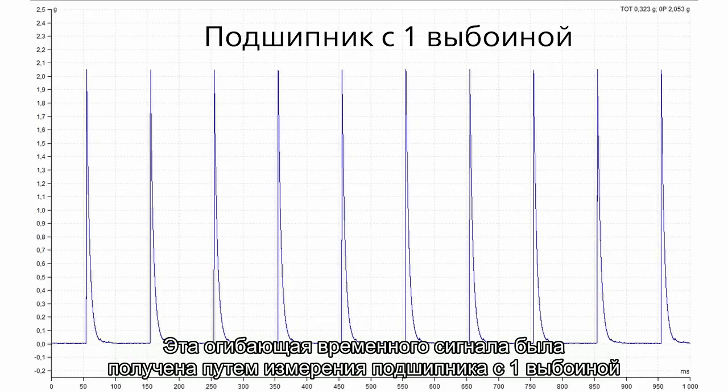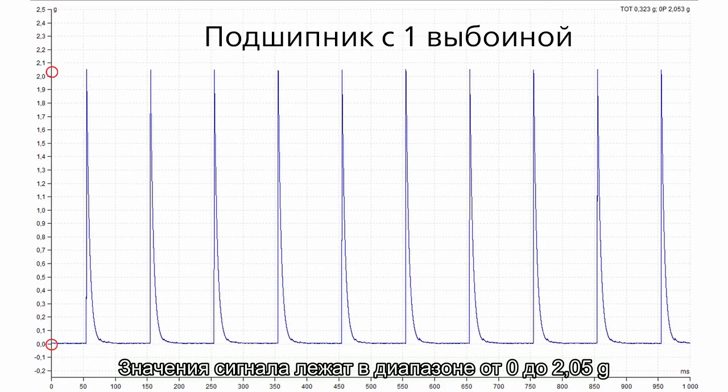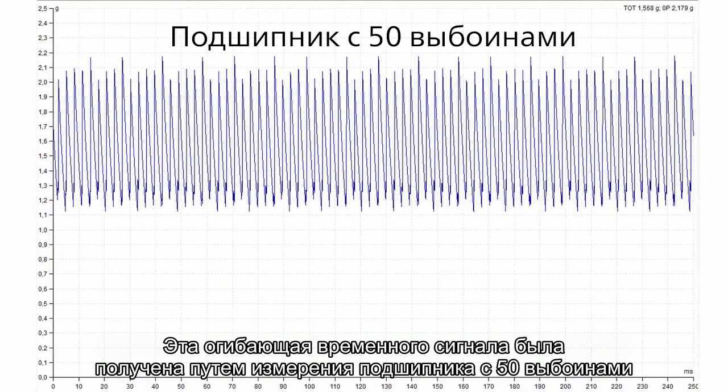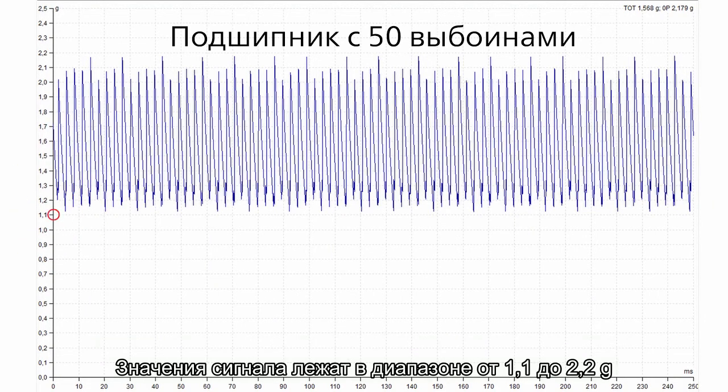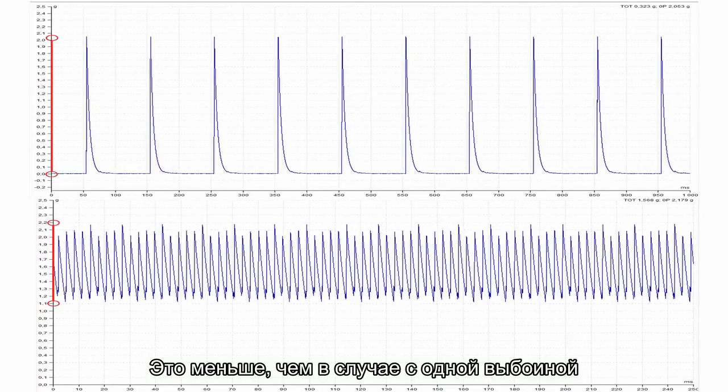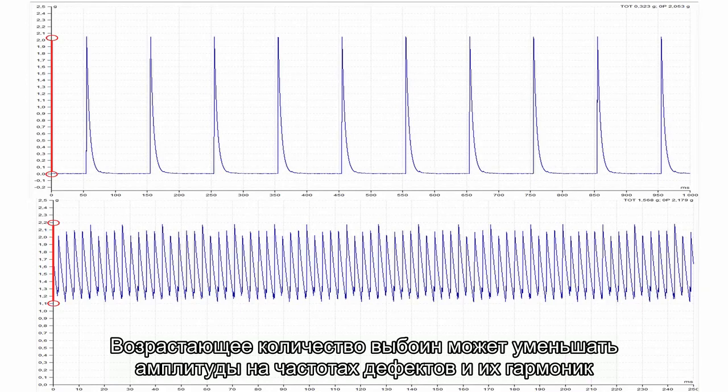This enveloped time signal was taken from the bearing with one crack. The signal range is from 0 to 2.05 G. This envelope time signal was taken from bearing with 50 cracks. The signal range is from 1.1 to 2.2 G. It means the peak-peak AC value is just 1.1 G. It is less than the case with one crack. And that is the trick. The increasing number of cracks can decrease the amplitudes on fault frequencies and harmonics.